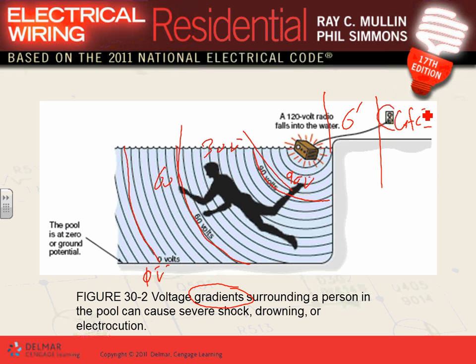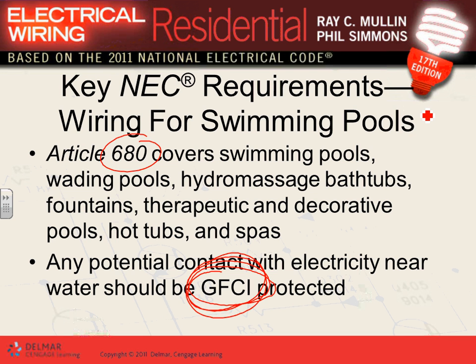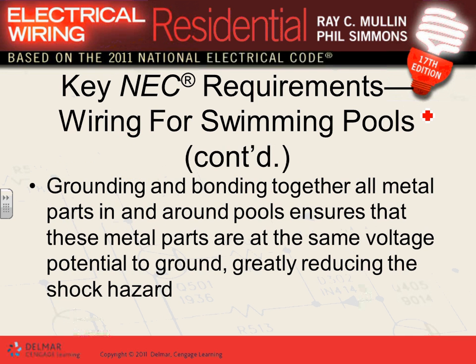So number 1, guys, they move the electrical equipment away from the swimming pool. That's protection number 1. Number 2, after they move them 6 feet, they put them on what? GFCI. So GFCI protection is very, very important in these locations. Then what they do, guys, is that they bond everything. They call it bonding the grid. They bond everything around the swimming pool.